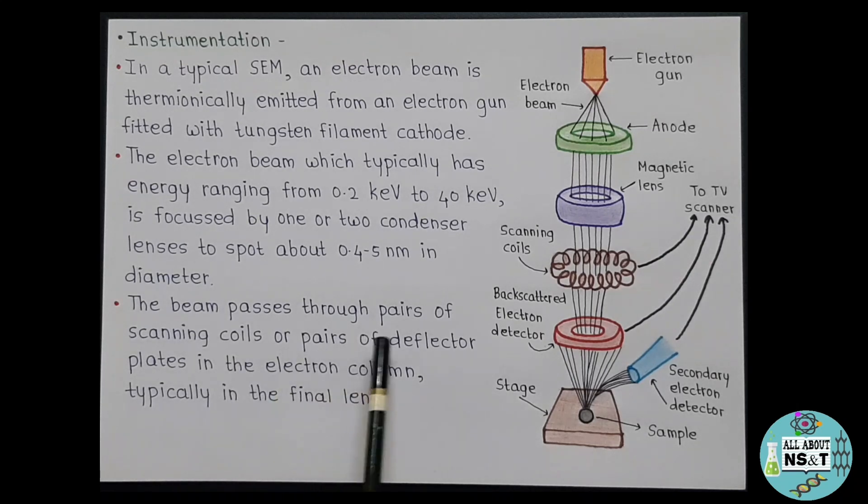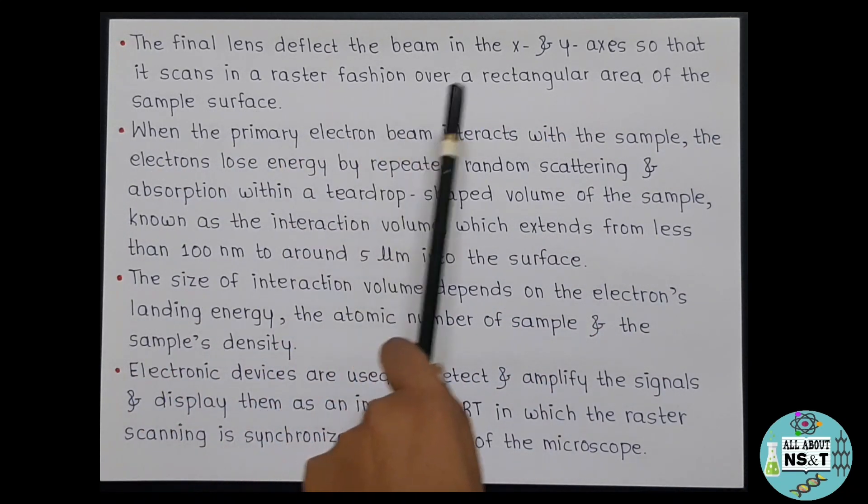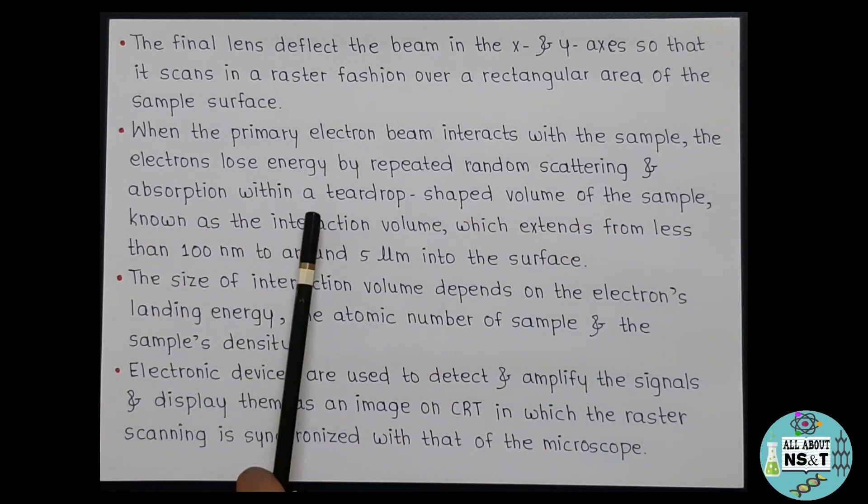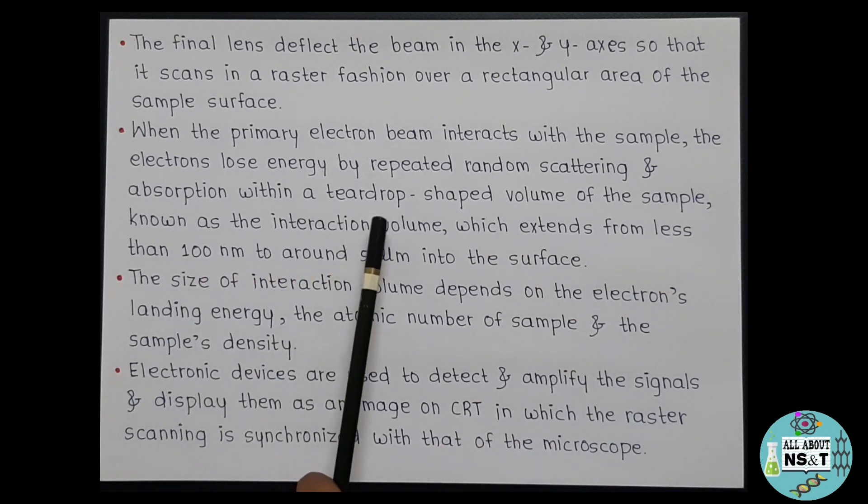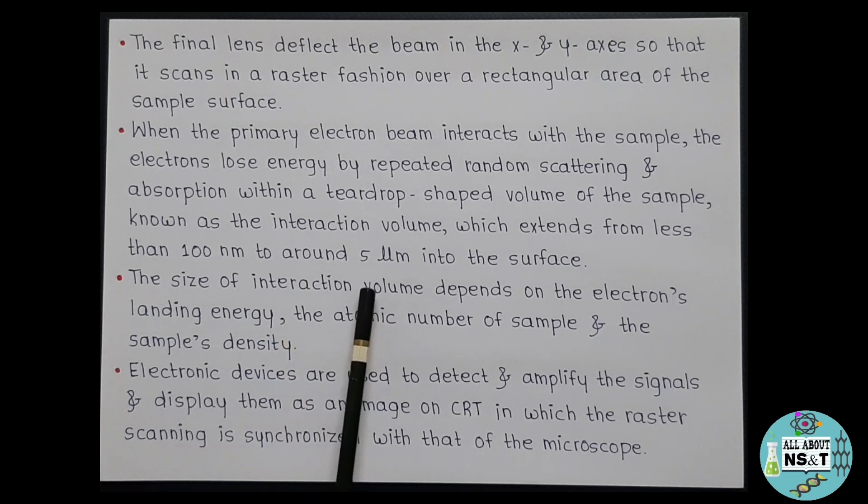Then the beam passes through pairs of scanning coils or pair of deflector plates in the electron column, typically in the final lens. The final lens then deflects the beam in the x and y axis so that it scans in a raster fashion over a rectangular area of the sample surface. When the primary electron beam interacts with the sample, the electrons lose energy by repeated random scattering and absorption within a teardrop shaped volume of the sample known as the interaction volume, which extends from less than 100 nanometers to around 5 micrometers into the surface. Here the size of interaction volume depends on the electron's landing energy, the atomic number of sample, and the sample's density. Various electronic devices are used to detect and amplify the signals and display them as an image on CRT, in which the raster scanning is synchronized with that of the microscope.